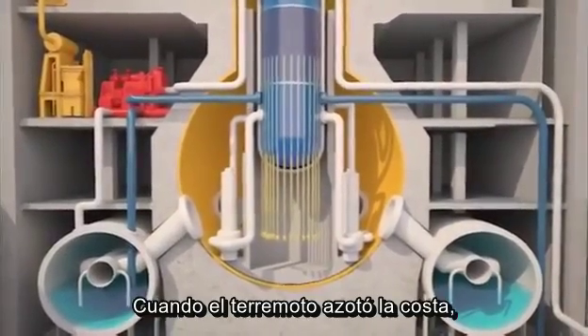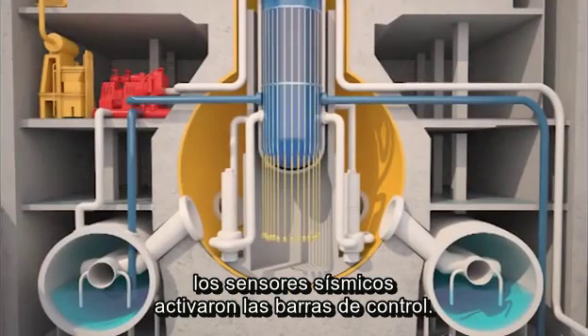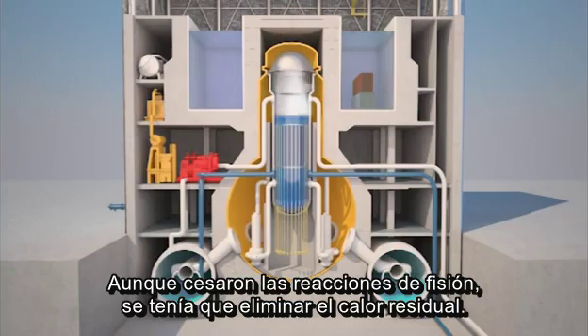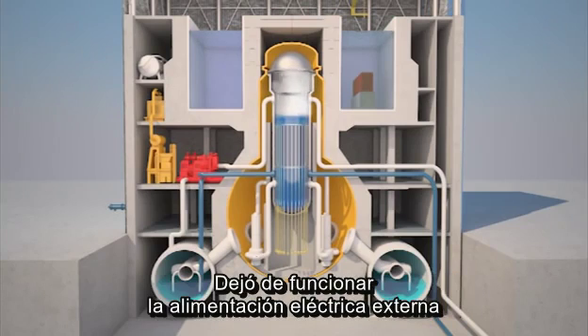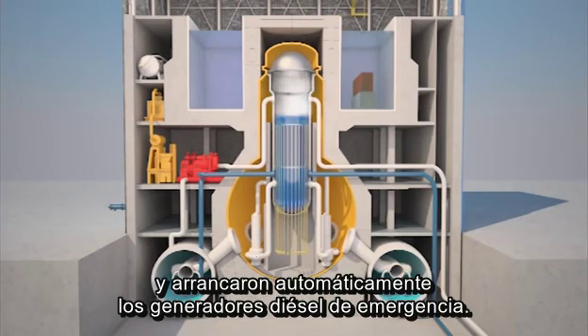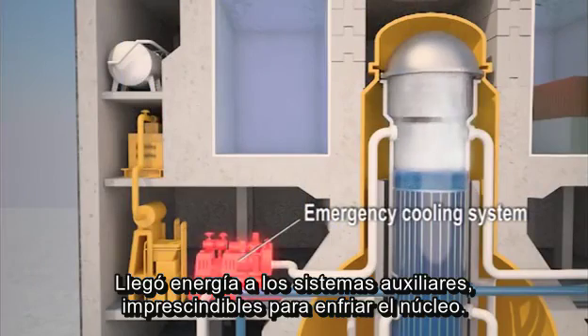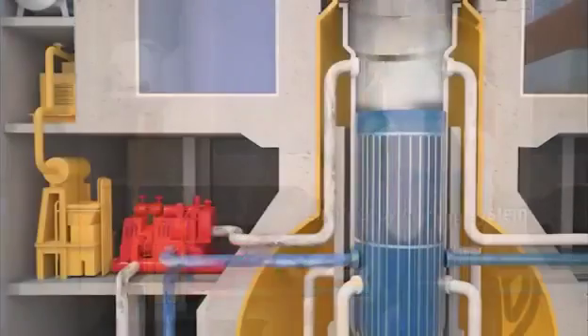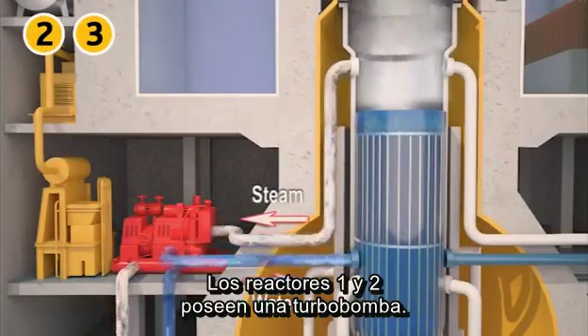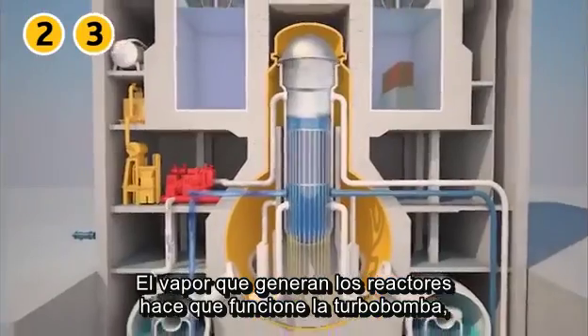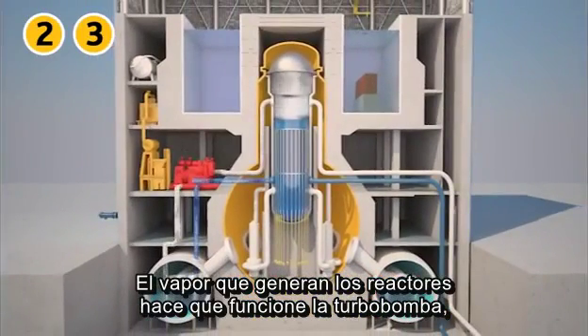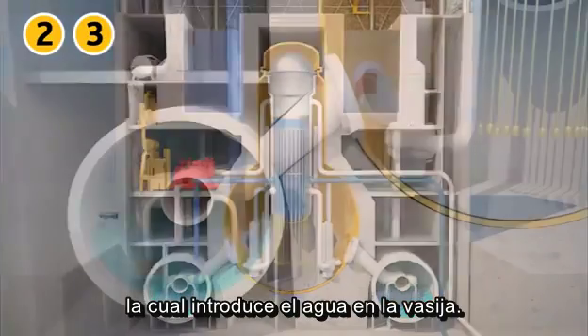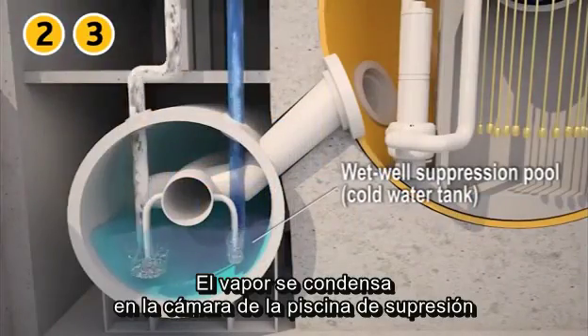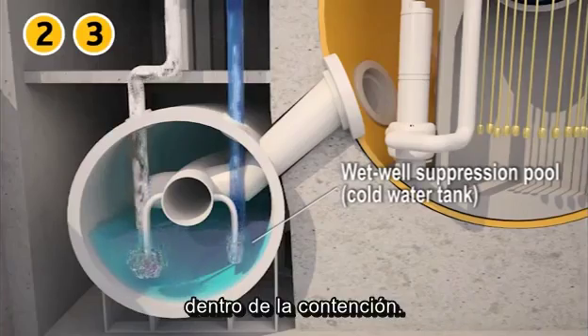When the earthquake hit the coast, seismic sensors triggered the insertion of control rods. Although fission reactions stopped, the residual heat had to be removed. The off-site power supply was lost, and the emergency diesel generators took over automatically. They supply electricity to the backup systems needed for core cooling. In reactors 2 and 3, it is a turbopump. The steam generated by the reactor operates the turbopump, which feeds water into the reactor vessel. The steam is condensed in the wet well suppression pool within the containment.